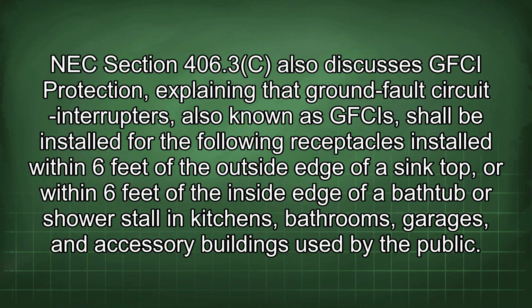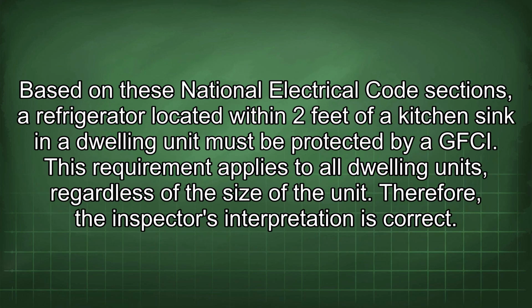NEC Section 406.3c also discusses GFCI protection, explaining that ground fault circuit interrupters, also known as GFCIs, shall be installed for the following receptacles installed within 6 feet of the outside edge of a sink top, or within 6 feet of the inside edge of a bathtub or shower stall in kitchens, bathrooms, garages, and accessory buildings used by the public. Based on these National Electrical Code sections, a refrigerator located within 2 feet of a kitchen sink in a dwelling unit must be protected by a GFCI.